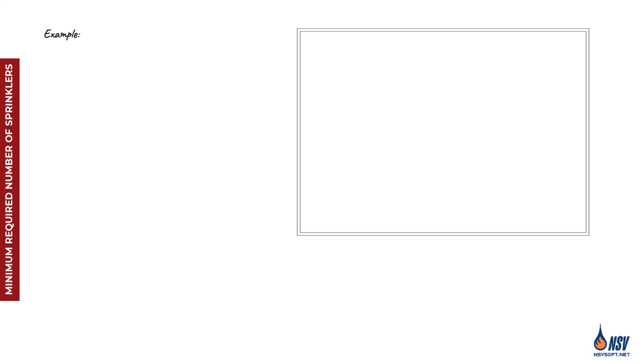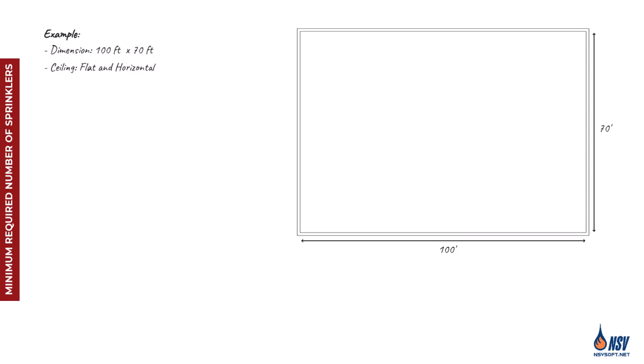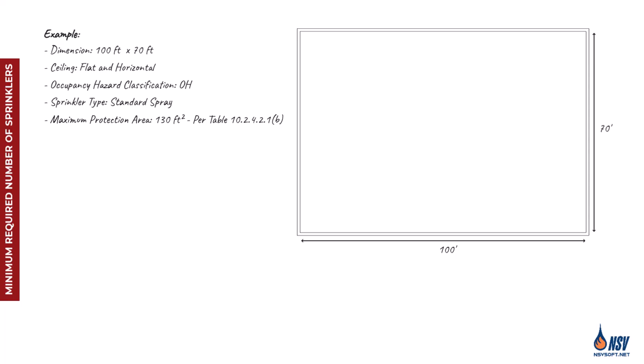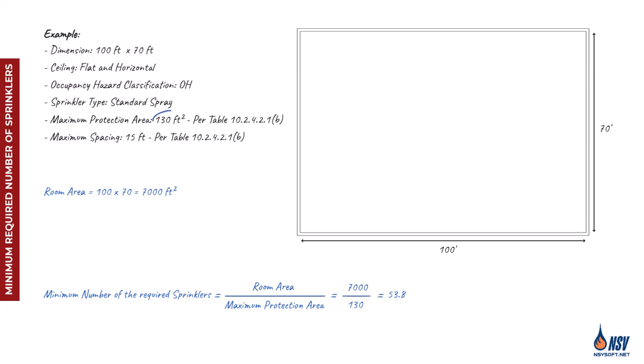Let's walk through an example to see how we calculate the minimum number of sprinklers required. We consider a room measuring 100 by 70 feet, featuring a flat horizontal ceiling in an ordinary hazard occupancy classification. The selected sprinkler type is standard spray. According to Table 10-2421B, the maximum coverage area per sprinkler is 130 square feet with a maximum spacing of 15 feet. The room's total area is 7,000 square feet. Dividing that by 130 gives approximately 53.8.